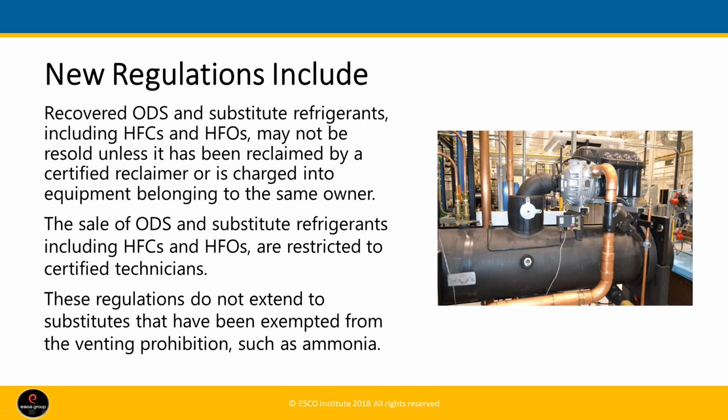Now, recovered refrigerant, just as before, cannot change ownership. It can be moved from one piece of equipment to another if it does not change ownership. The only thing I would be careful about is warranty, because some manufacturers will not warranty the equipment if they find out you've used refrigerant that has been in another piece of equipment.